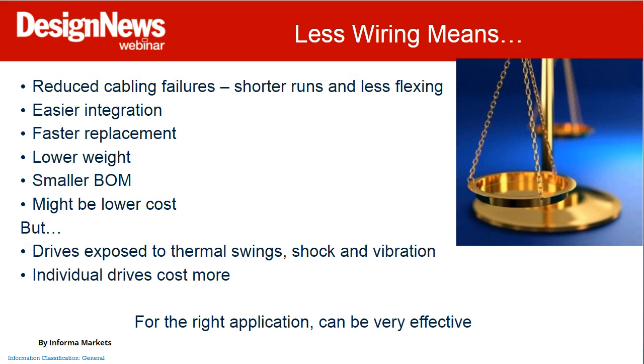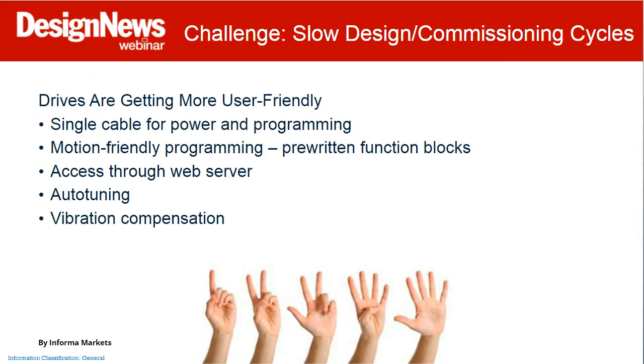Another thing—we were talking about speeding up your design and commissioning cycles. So drives, and indeed all motion components, are really getting more and more user-friendly. There's a drive toward consolidating power and programming down to a single cable. There's motion-friendly programming with pre-written code blocks, and that extends even into the control space. There's PLCOpen, which has whole libraries of motion code blocks in multiple languages—structured text, ladder logic, and function block. So it's all there to use.